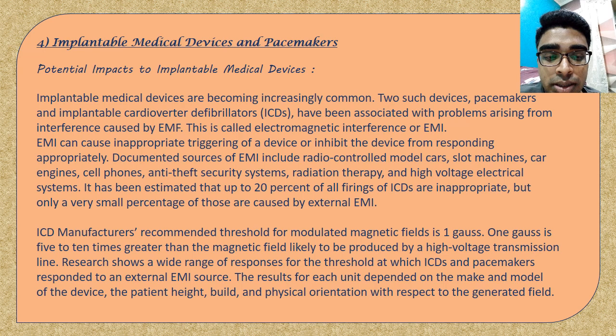Two such devices, pacemakers and implantable cardioverter defibrillators (ICDs), have been associated with problems arising from interference caused by EMF. This is called electromagnetic interference, or EMI. EMI can cause inappropriate triggering of a device or inhibit it from responding appropriately.